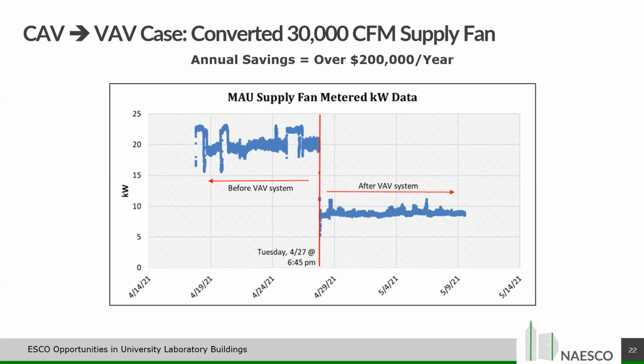Another way of measuring another case study is basically monitoring or trending the supply VFD and seeing what that VFD does. Kind of self-explanatory on what we're able to do there. Basically, again, pre-VAV system, constant volume, where that VFD was running. And then once we took control of the system and slowed everything down, you see the post to the right of the red line.